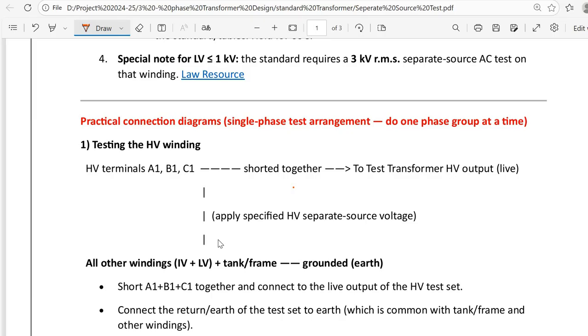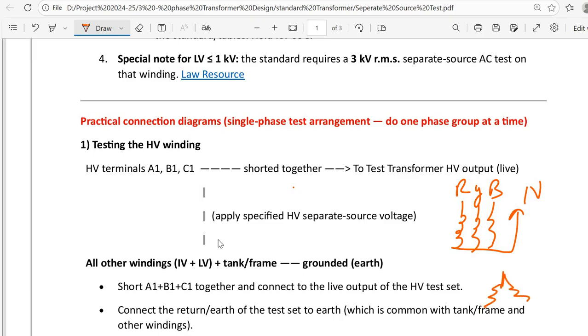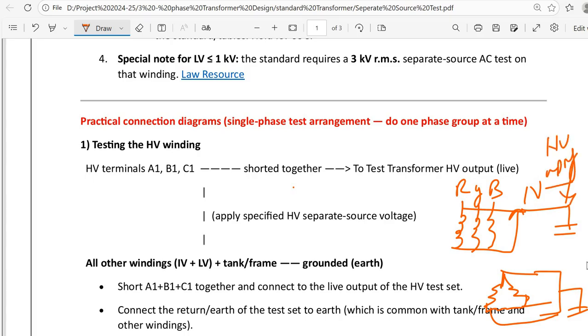In this way you can test separate source and test the HV winding. If this is the three-phase transformer, with R, Y, B and neutral, and the other is the LV winding, meaning delta, all are shorted together. If you want to do the separate source test of HV, the HV supply goes here and the other is ground. In this way you can easily test.